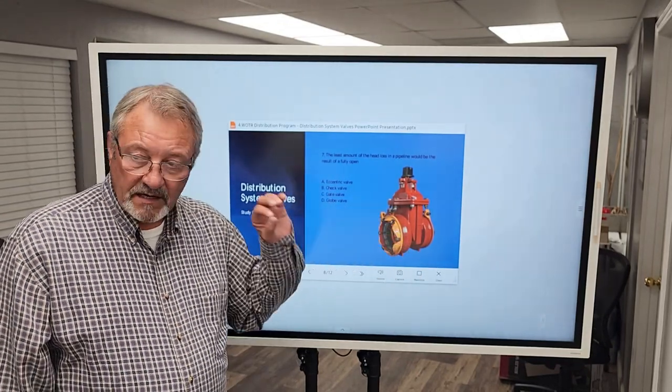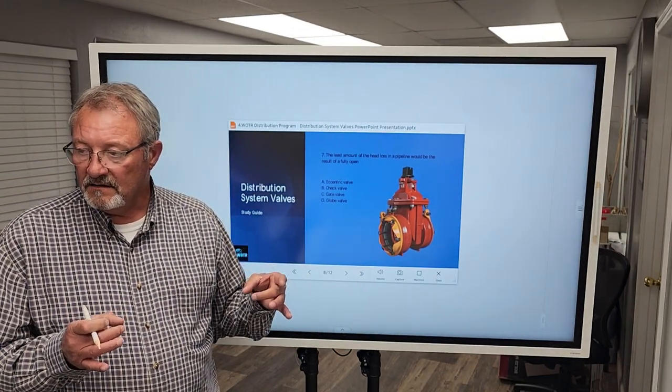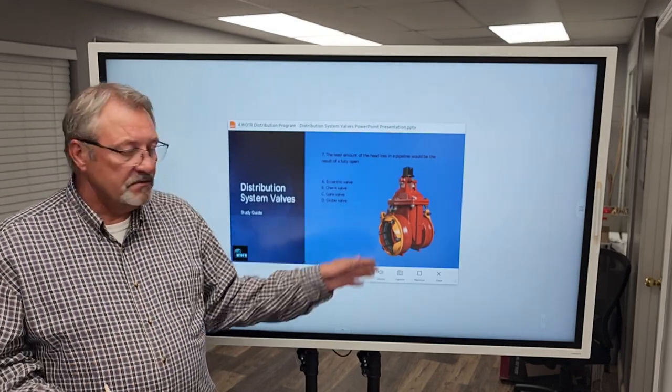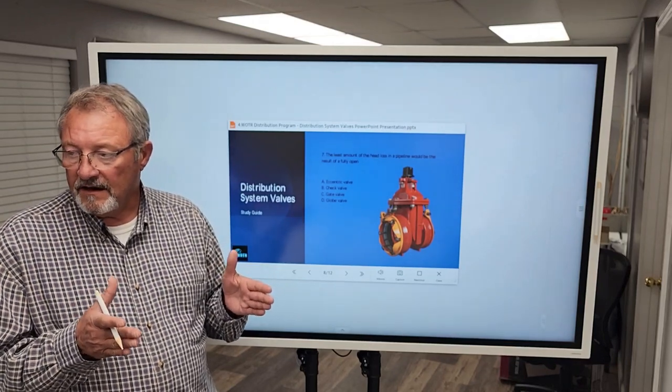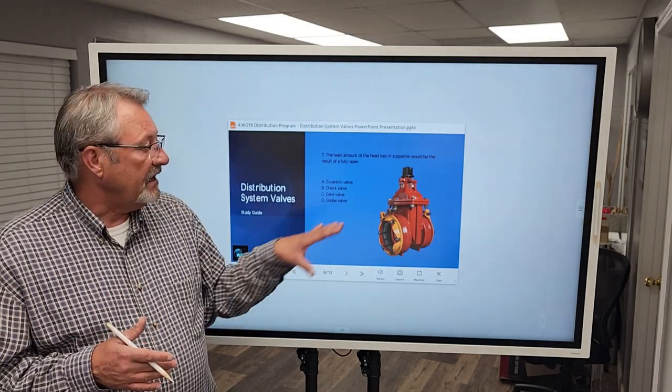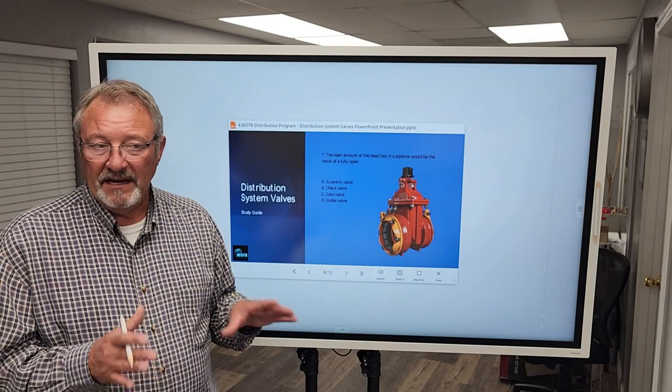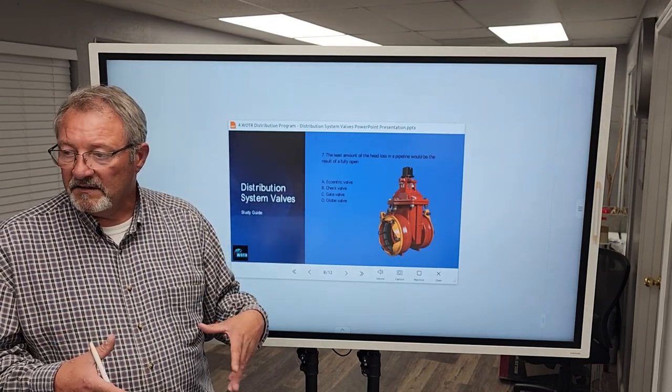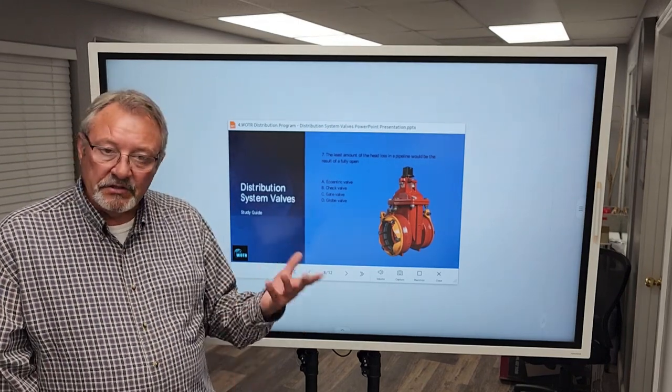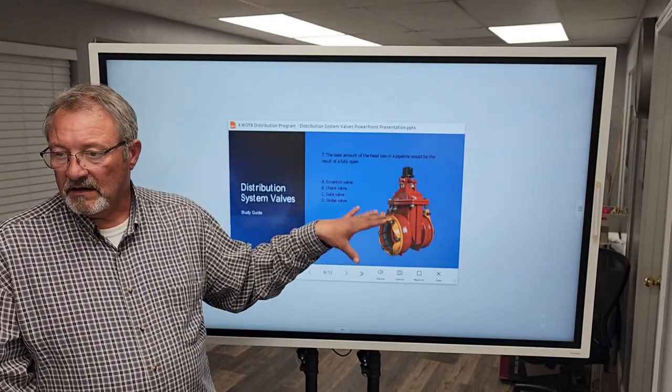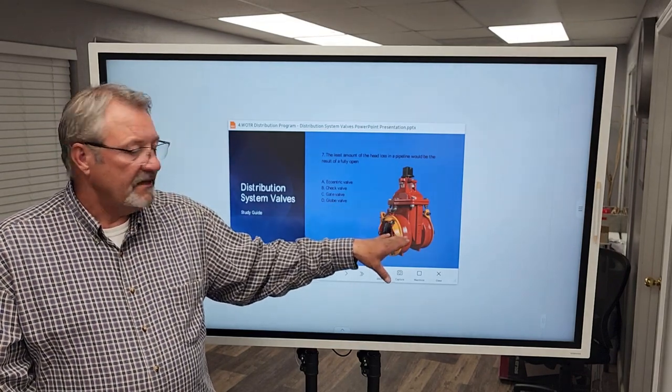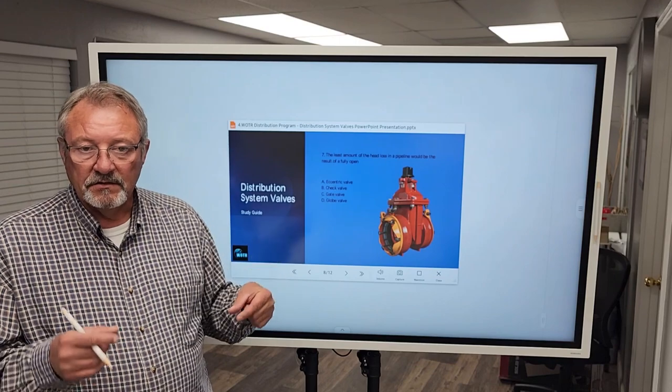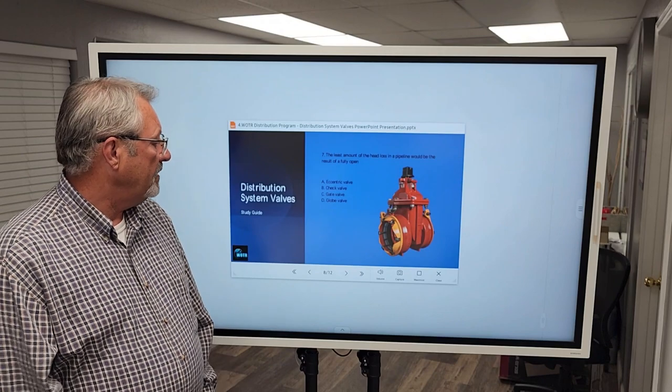There's different types of gate valves. One of those gate valves has a gate that has wedged sides. And with those wedged sides, as you close it, it locks that gate in place and closes and isolates that section of pipe. And those types of gate valves, while gate valves typically aren't used to throttle flows, they're not made for that because the flow of water actually degrades the sides of the gates, making them less effective. So we don't really want to throttle flows with them. We do, but we don't want to. In those situations we're changing those out with plug valves. Plugs are more effective at throttling flow. But the gate valves with the wedged sides or the wedged closure element, it can be used for throttling flows.